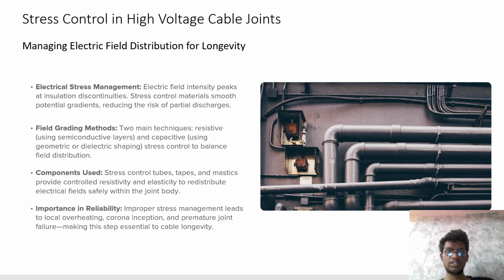Stress control in high voltage cable joints: managing electric field distribution. Electrical stress management: electric field intensity peaks at insulation discontinuities. Stress control materials create a smooth potential gradient, reducing the risk of partial discharge. Field grading methods: two main techniques, resistive, using semiconductor layers, and capacitive, using geometric or dielectric shaping, to balance field distribution. Components used: stress control tube, tape, and mastic provide controlled resistivity and elasticity to distribute the electrical field safely within the joint body. Importance in reliability: improper stress management leads to local overheating, corona inception, and joint failure, making these steps essential to cable longevity.